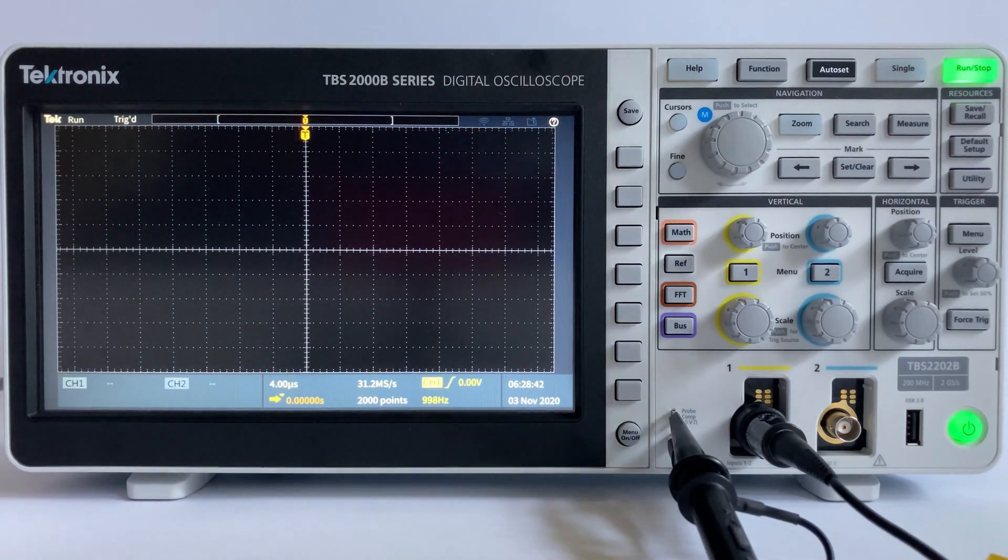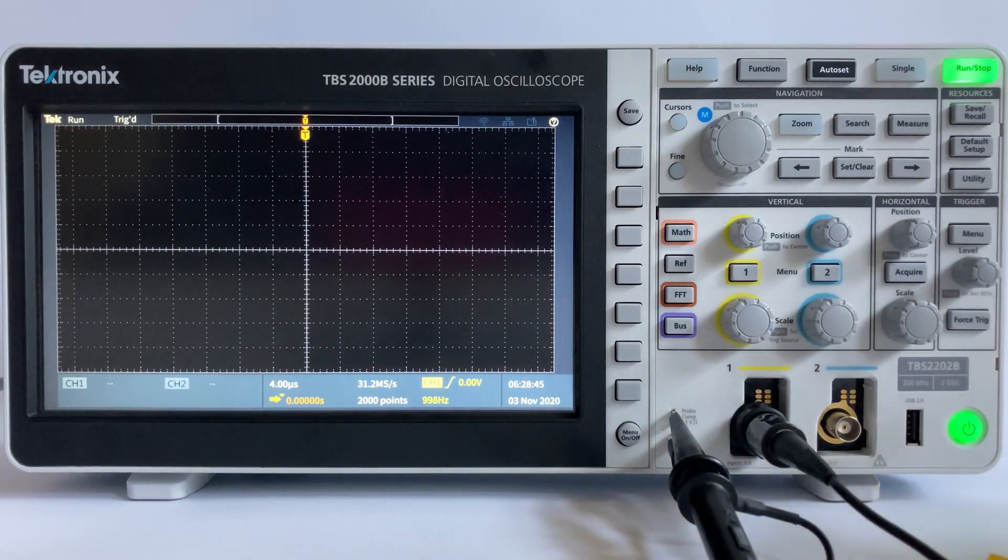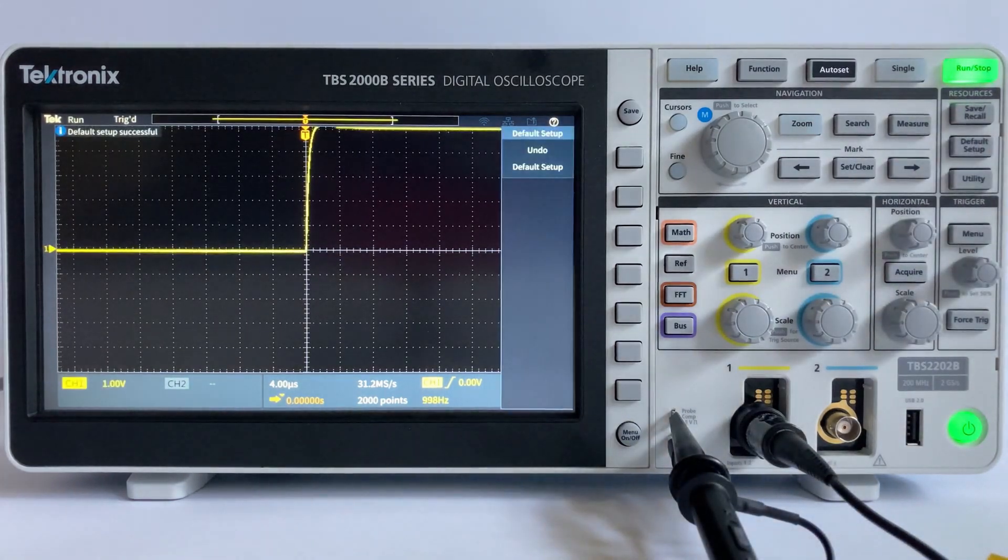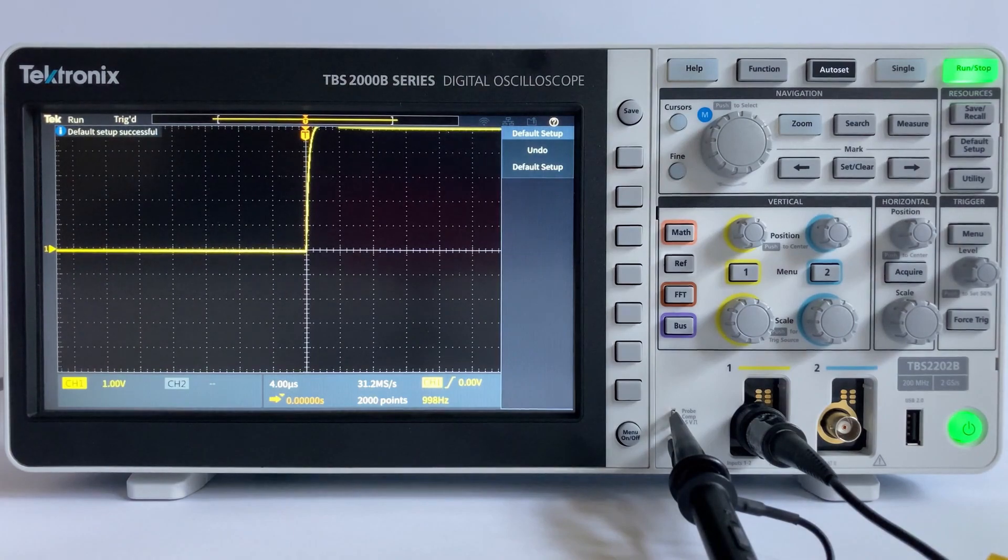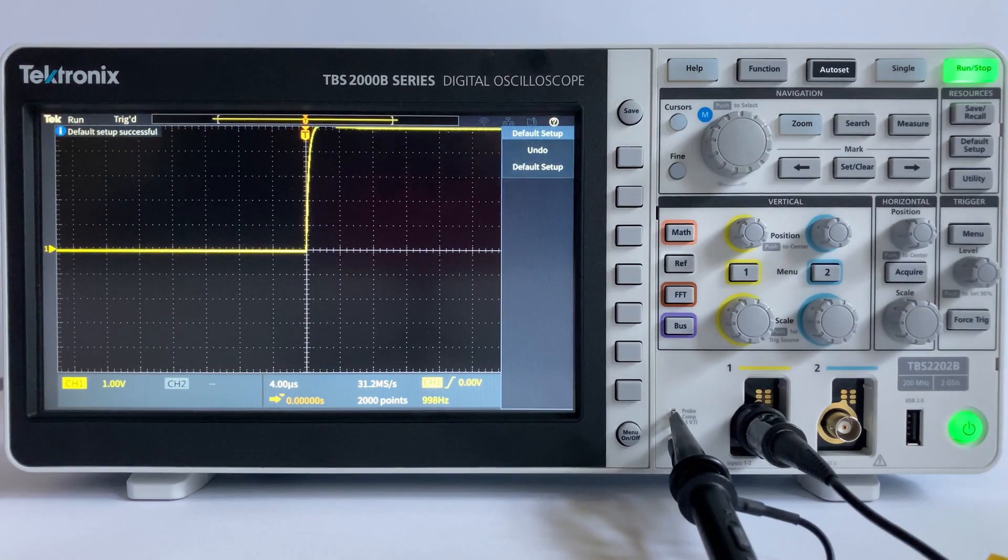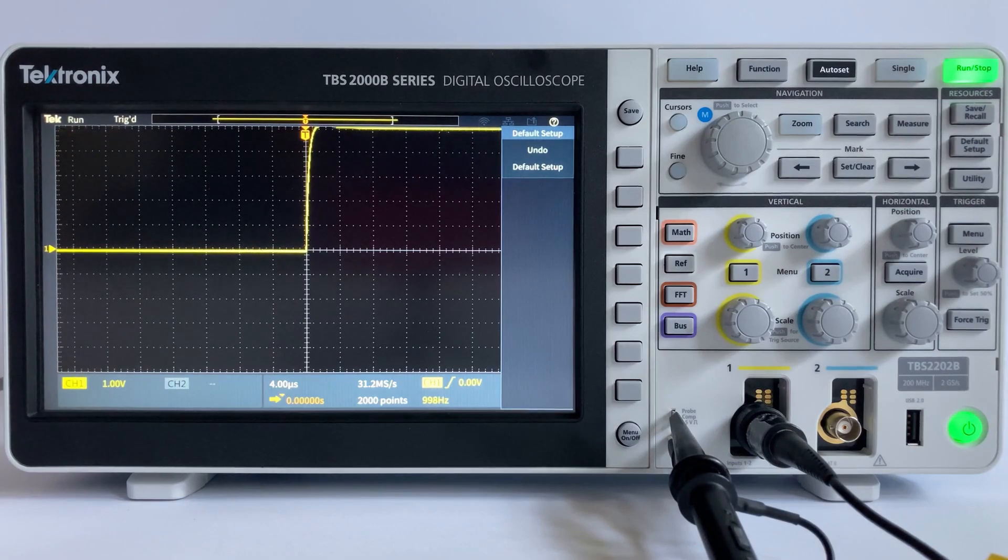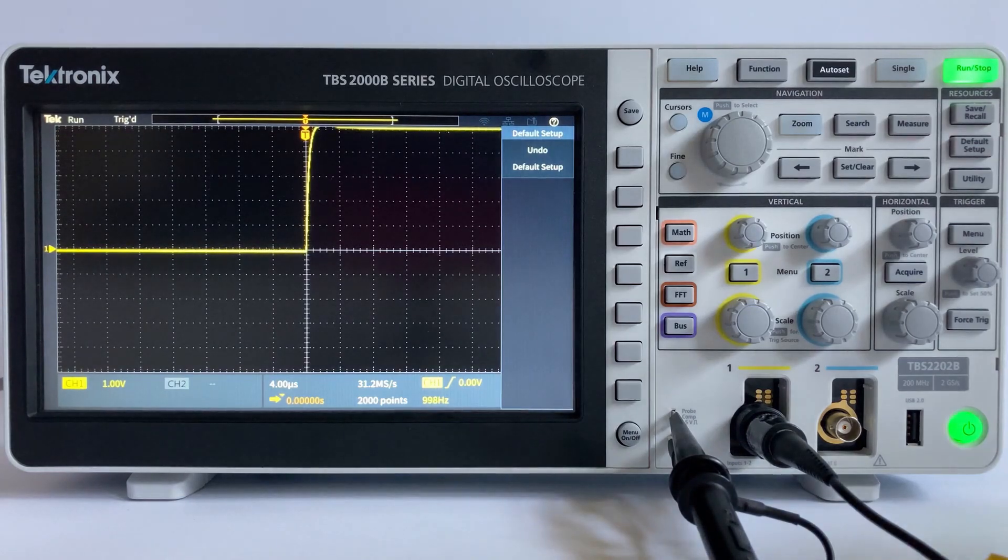First, let's push the default setup button in the resource section of the front panel. This will set the scope to its default state: 1V per division vertically and 4 microseconds per division horizontally. Now press Autoset at the top of the front panel to automatically scale and display the signal.